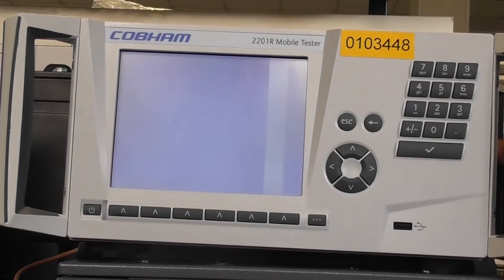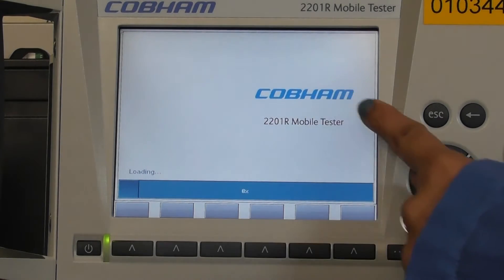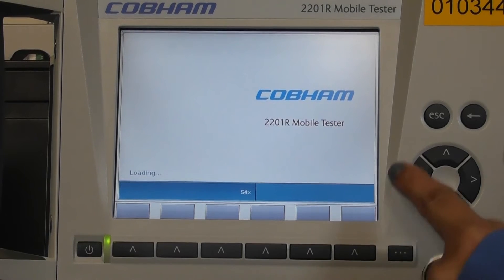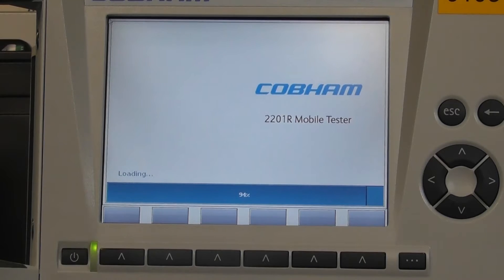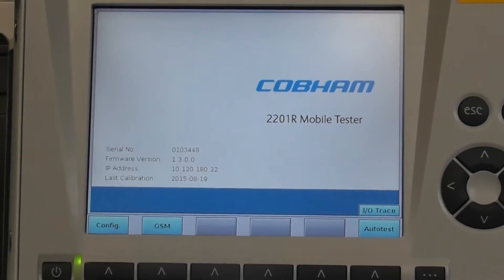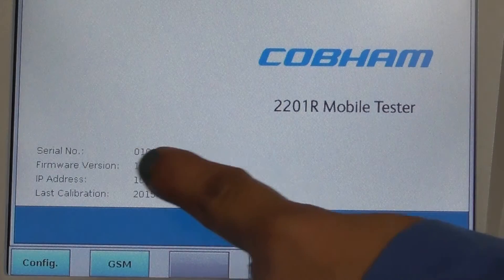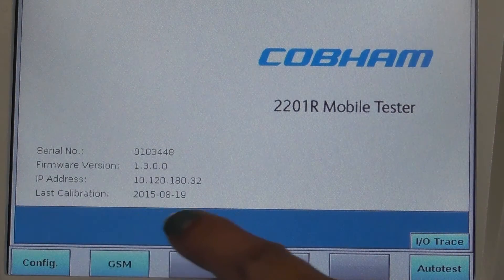We can power on the hardware now. The Cobham 2201R mobile tester — the loading progress bar shows that the firmware on this hardware is being loaded. After loading, you can see the serial number of the hardware, the firmware version, the IP address, and the last calibration date.